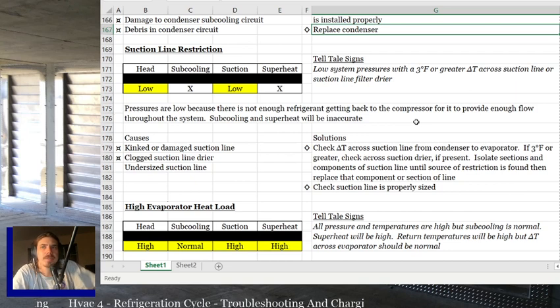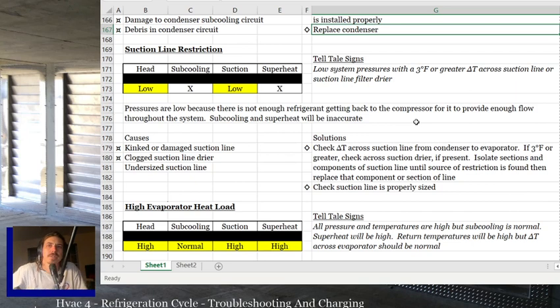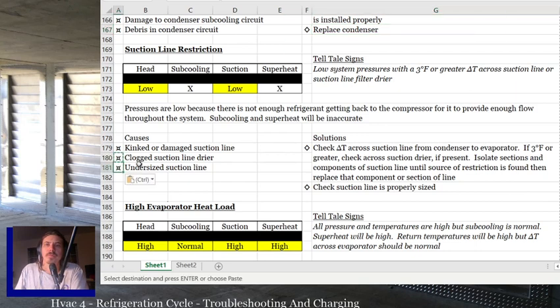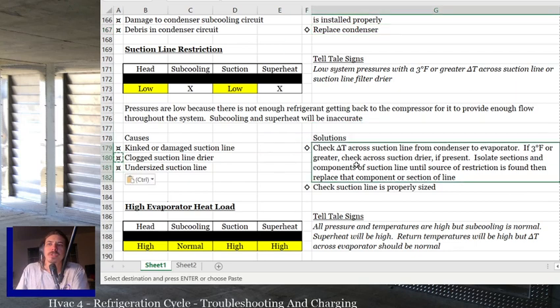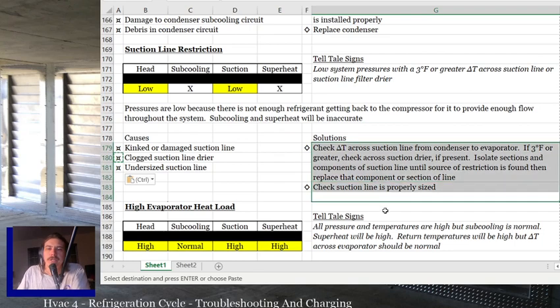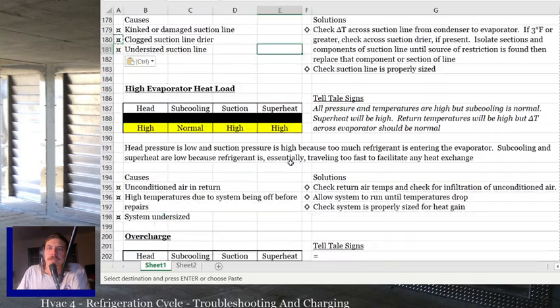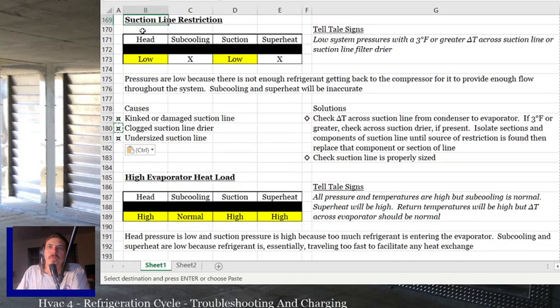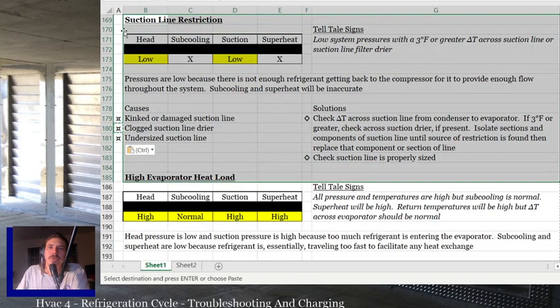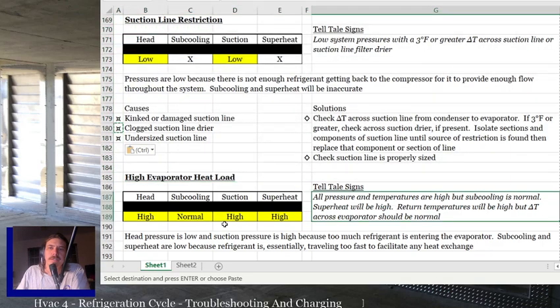The pressures are low because there's not enough refrigerant getting back to the compressor for it to provide enough flow throughout the system. Subcooling and superheat would just be inaccurate. A kinked or damaged suction line, a clogged suction line dryer, or an undersized suction line are going to be your problems. The solution is to check for delta T across the suction line and any components in the suction line, and to check if it's properly sized. So if you get that weird one day where you thought it was undercharged but it's not, double check that.